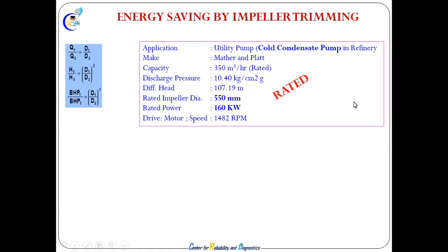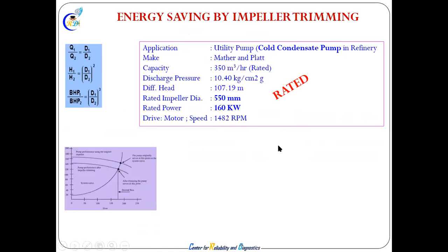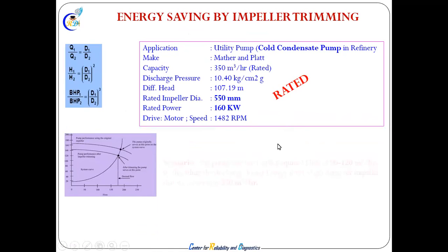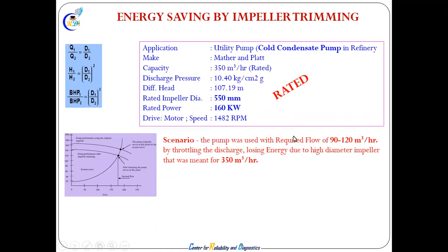This is a case of a condensate pump in a refinery in Gujarat. So they have done it. Initially, they purchased a 550 millimeter diameter impeller with a rated power of 160, and at 480 RPM they needed 100-something. The refinery and the commissioning team thought of this, but over time they thought no, this is not required. And the cost-benefit analysis showed that purchasing a new pump would cost more.